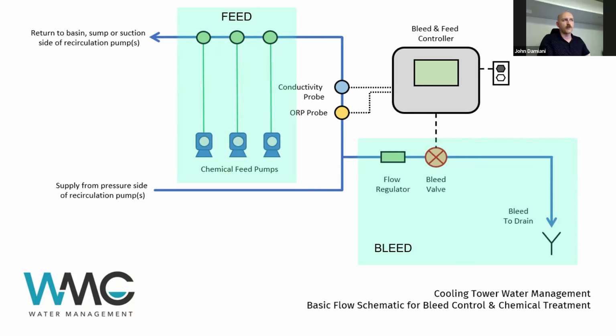So now, as the new makeup comes in, or according to other parameters, I'm showing an ORP probe there as well, so that would be a live way to control one of the biocides. But a lot of the products are fed, for example, proportionally. So you'd feed every 10 liters or 10 gallons of water, you'd have a meter that's sending a ping back to the controller to indicate that new water's entered the system that needs treatment. And then we'd activate our pumps, for example, to run product into there. And that optimizes the chemistry.